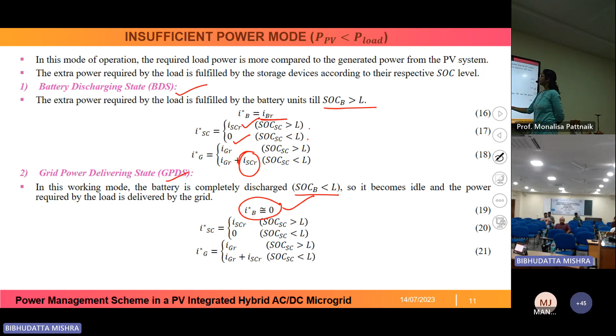When the battery is completely discharged, that means when the battery SOC is less than its lower limit, we make the reference zero so that the battery cannot supply power to the system. This is done to avoid deep discharging of the battery. Similarly for the supercapacitor, when its SOC is greater than its lower limit, it will supply the transient powers to the system. When it is completely discharged, it will not supply any power to the system, and the transient power should be supplied by the grid. Here we can see that along with the grid reference power, we have added this amount of transient power from the grid. A similar case will be there in the grid power absorbing state and power delivering state.